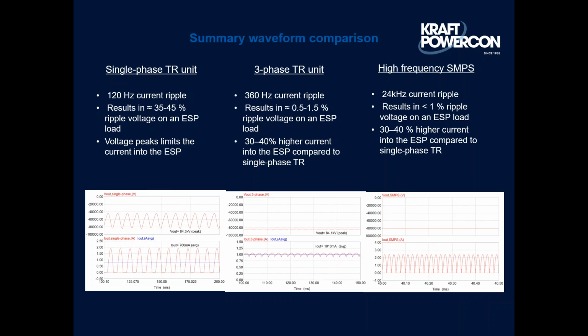We had an existing precipitator on an existing boiler, and it had to perform better. So we had to move to the right on this page, away from the variable waveform of the single phase TR towards something flatter and more DC-like, as you see on the two to the right. The early available units were typically high frequency switch mode power supplies. So we moved from something simple to something more complex, difficult, and initially, less reliable. But that has changed over the years, and those high frequency switch mode power supplies are more reliable now.